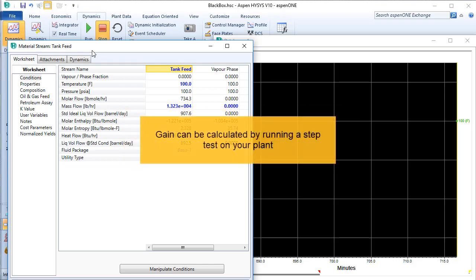If I didn't know the gain, I could input a step change to the plant and wait for the process to stabilize, then measure the corresponding change in the outlet.